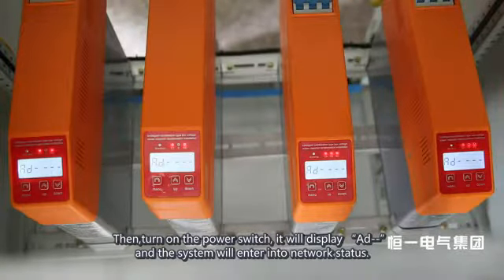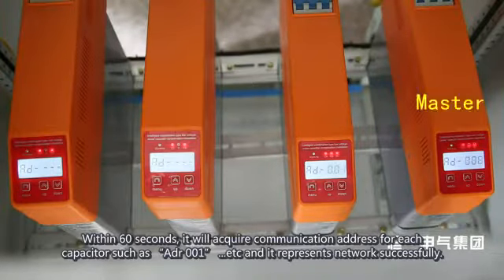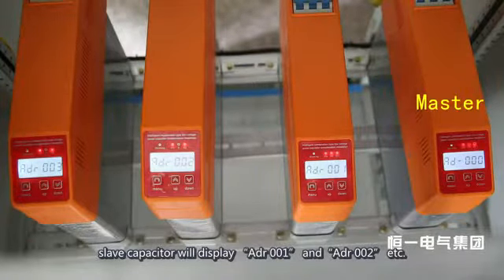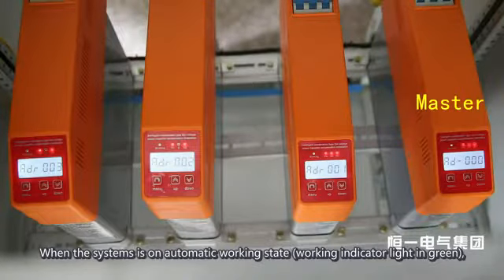The display will show 'Ad--' and the system will enter network status within 60 seconds, acquiring a communication address for each capacitor — such as ADR 001, etc. — indicating successful networking. When phase-splitting compensation type capacitors are in network status, they will display ADR 001, ADR 002, etc. When the system is in automatic working state, the working indicator light is green.